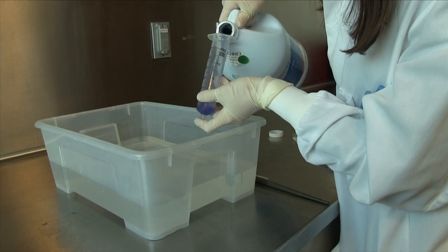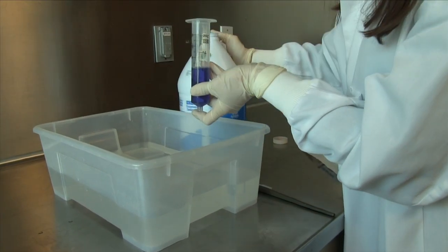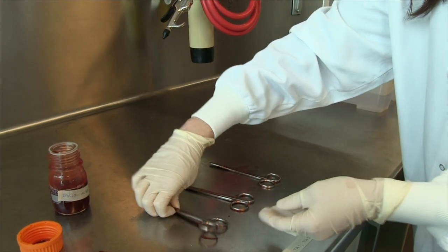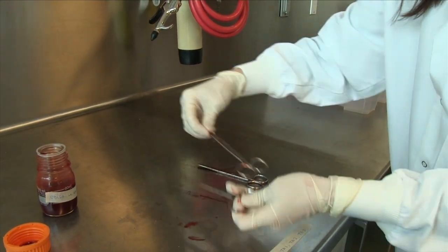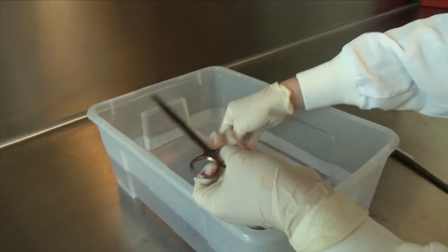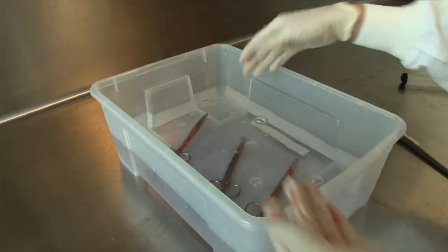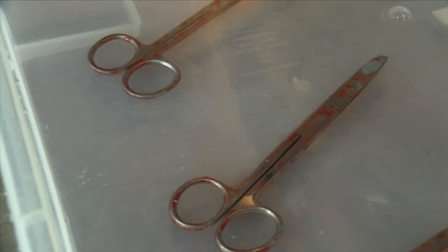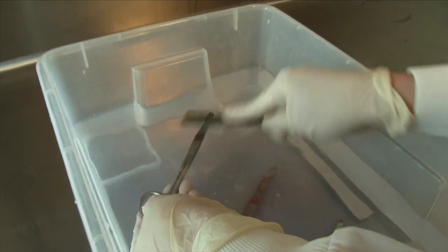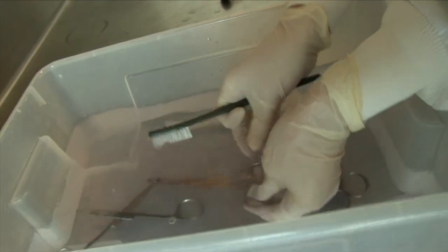Another step for worst case is in the cleaning process. We want to make sure that before attempting a very involved, elaborate cleaning, that we are attempting to do the detergent manufacturer's labeled minimum soak times and minimum procedures that are going to define the minimum for the actual instructions for use for these devices. Extraction efficiency is another area that the FDA wants to see.